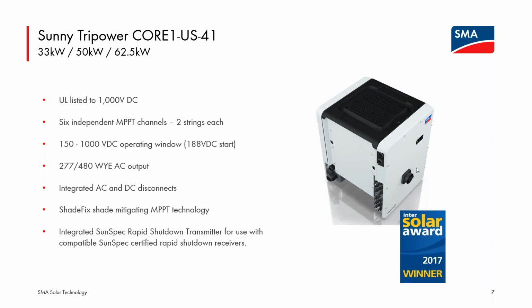You have the DC disconnect built right into the body of the inverter. And on the opposite side of the US models, there is an AC disconnect as well. So you have load break rated DC and AC disconnects built into the inverter. No need to have an additional piece of equipment near the inverter wired up to it, worry about where it's mounted, it's all included. So no need for a combiner box, DC disconnects included, AC disconnect is included. Like I said, a lot of effort went to ensuring that this was very much an all-in-one, very easy to install inverter.